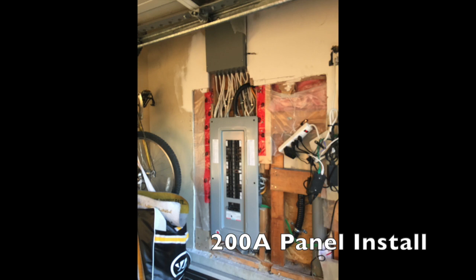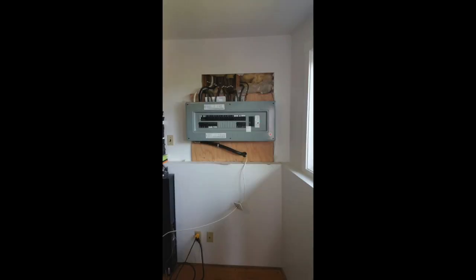These sometimes have to be installed according to the length of the original wires. The extension of the original electrical wires using the junction box allows us to stay within today's current code, which only allows us to go 1700 millimeters to the top breaker, and we cannot go any higher than that 1700 millimeters. In some scenarios, the panel may have to be installed horizontal to meet code requirements.